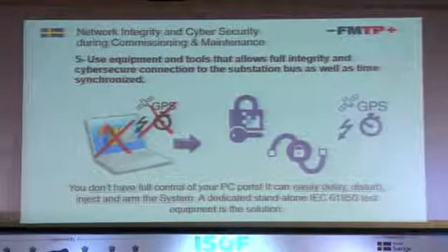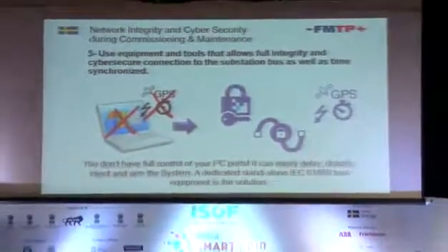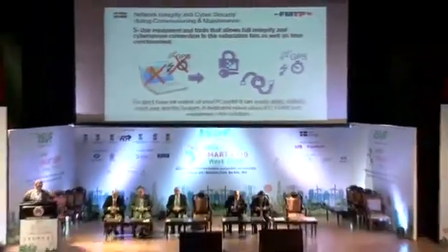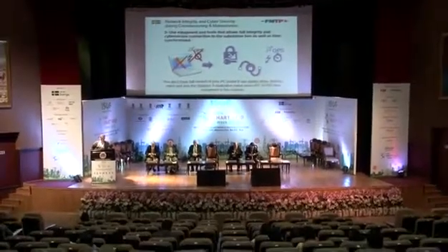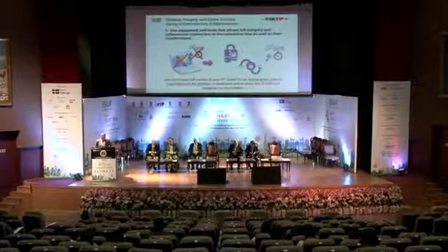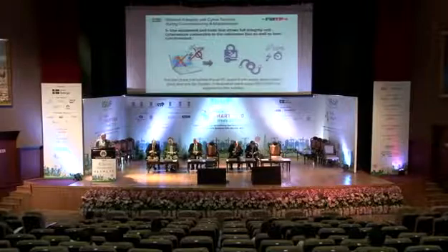My customer asked me since 2 years ago, are you safe to connect to my station? And I say, yes, I can, because it's not a PC. So our tool needs to not be a PC. It needs to be dedicated. It needs to be safe, in the sense that we are sure that we are not publishing information, because if we publish something not declared in the SCD file, the other equipment in the station will not recognize us, and that will create a disturbance, and we don't want those disturbances.